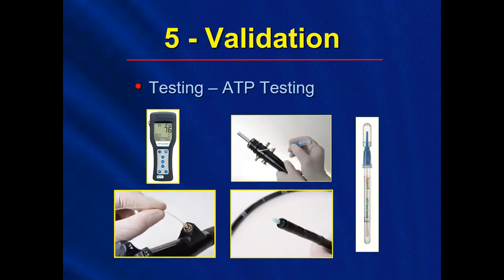Now, devices that measure ATP, adenosine triphosphate, again, it's an excellent means of verifying that your cleaning processes have been effective. ATP devices have the ability to test the external surface of anything with the use of a swab, as you see on the right there. Some devices actually have the capability of testing the inner lumens of scopes and other cannulated instruments with the use of a test sponge, as shown here. You'll see a test sponge going inside of a flexible scope. And that test sponge can actually be used to test ATP inside the lumens of the scope.